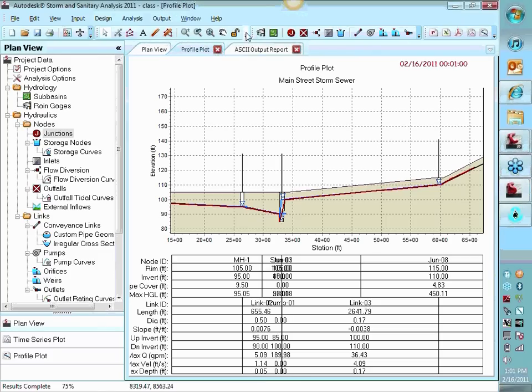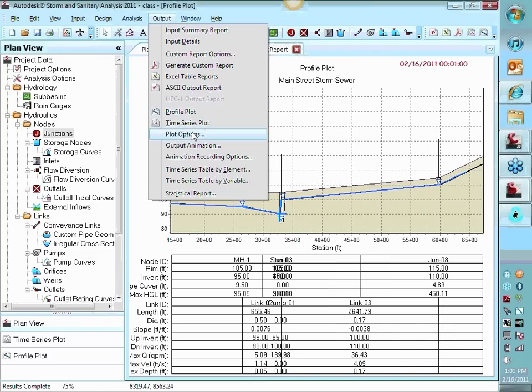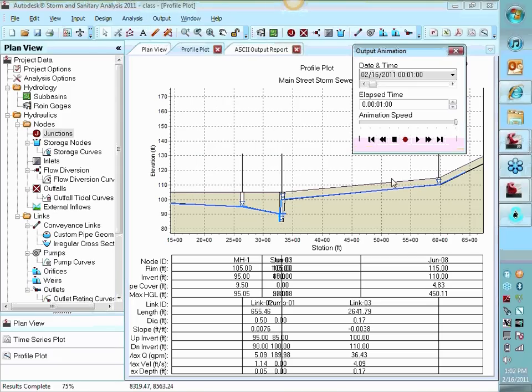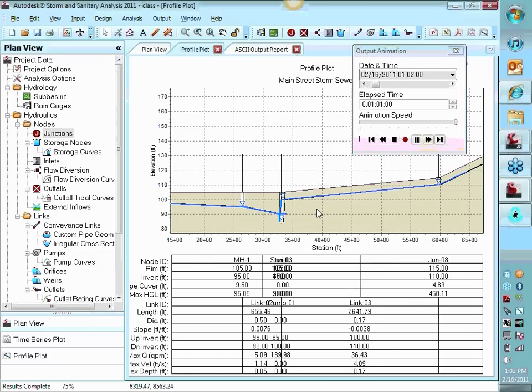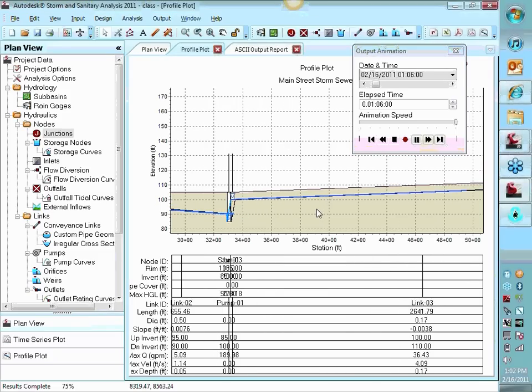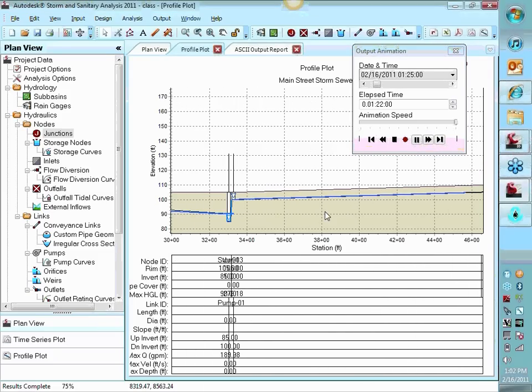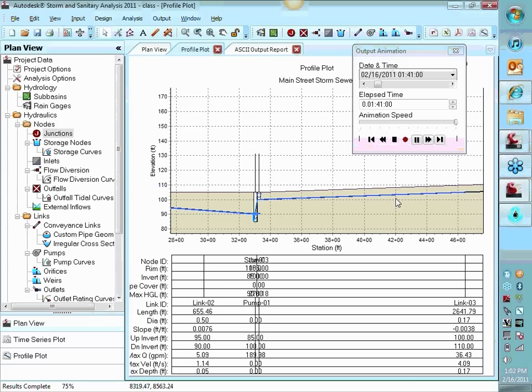And then you can run your system again. You can see now we're getting velocities. Getting velocities down here for max velocity in our force main. So four feet per second. Not too bad.